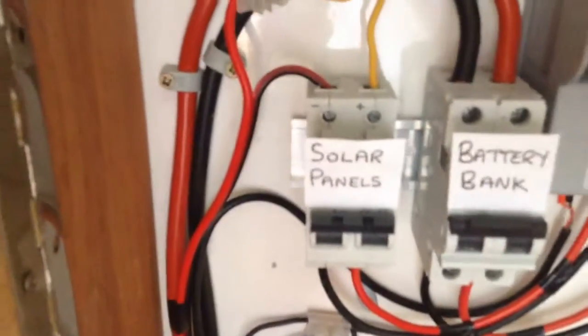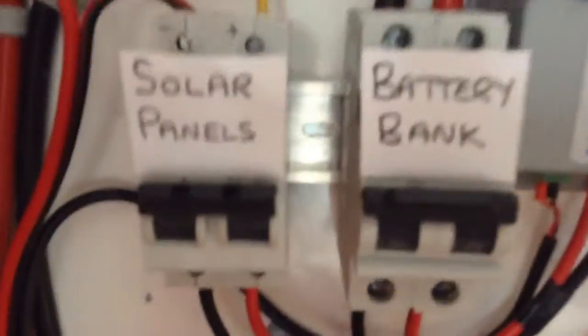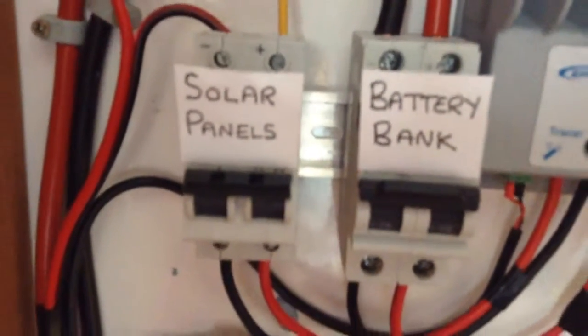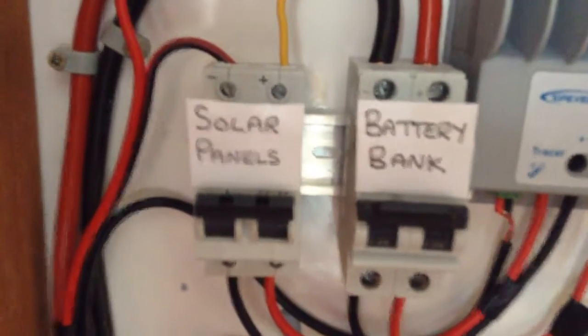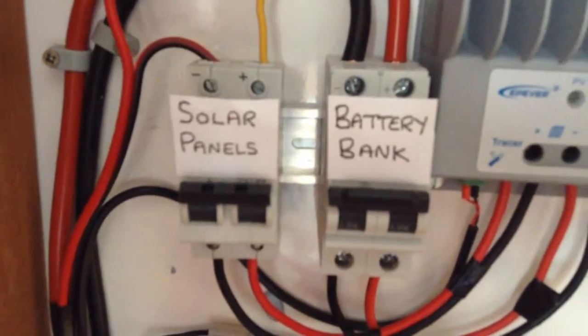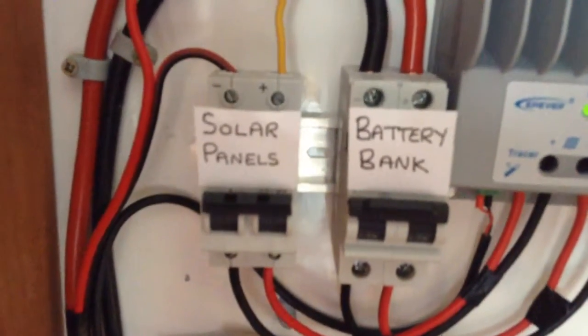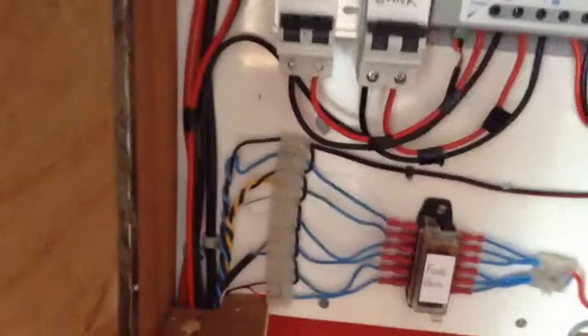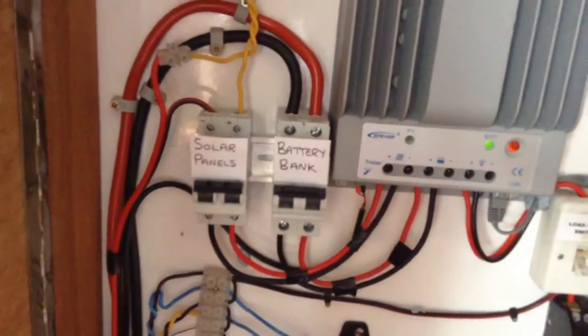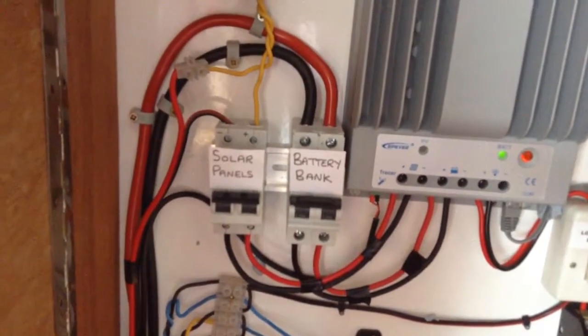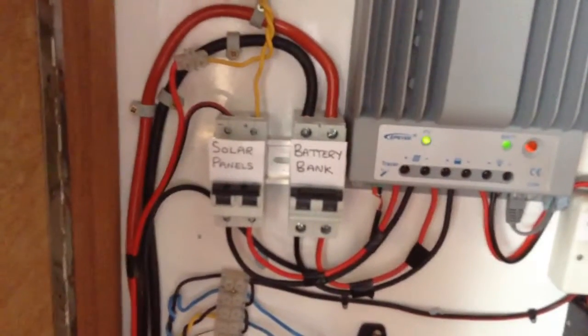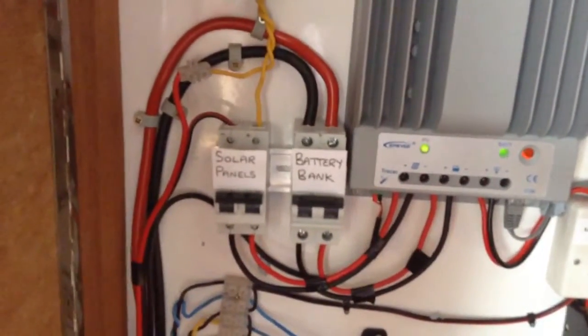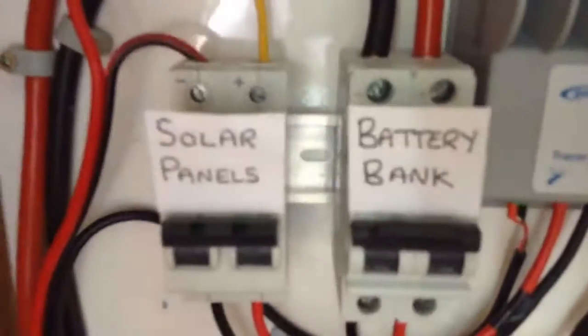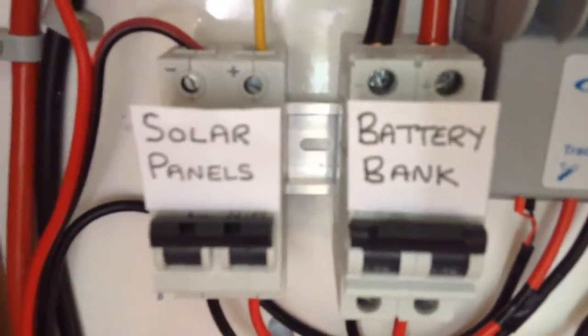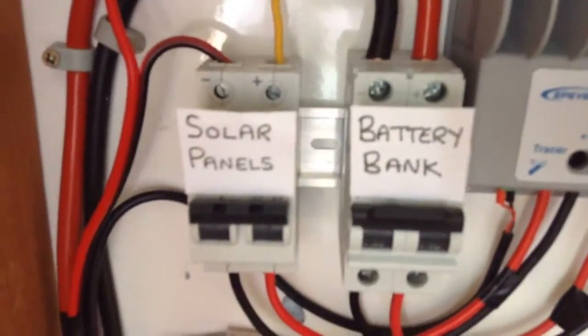My panels can only produce about 6 amps, so that's okay. But one thing to note is that these are proper DC circuit breakers. Do not use AC breakers on DC circuits - they just don't work properly, the DC breakers are built differently inside, as it is harder to interrupt a DC circuit than an AC one. And these DC breakers are not that expensive - it cost me about 10 British pounds.